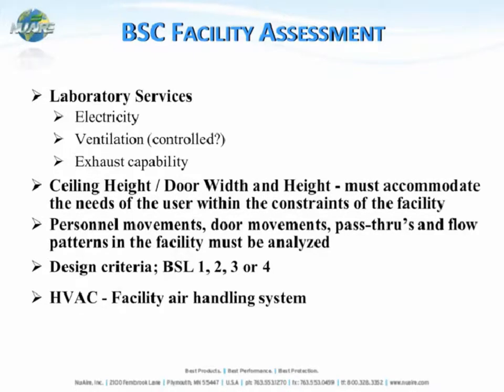Also look at personnel movements within the lab — door movements, pass-throughs, and airflow patterns must all be analyzed. Look at the design criteria: is it a BSL 1, 2, 3, or 4 space? And you must look at the HVAC facility air handling system to ensure that if you require exhaust to the outside, it can handle the exhaust requirement of that particular biological safety cabinet.